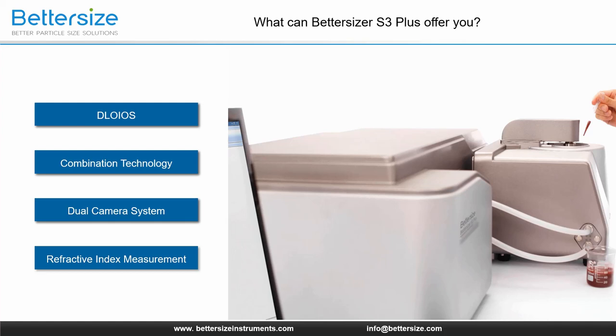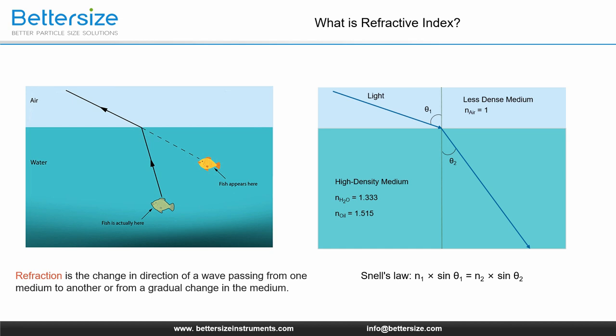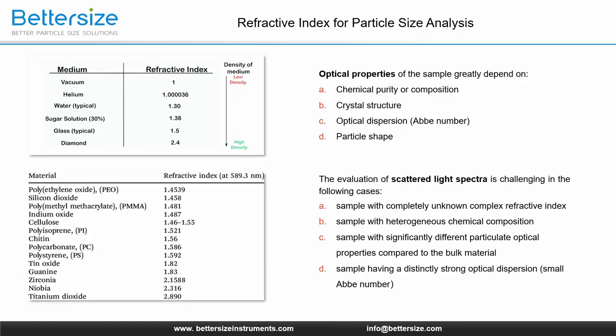I'm going to introduce a very special feature of the Bettersizer S3 Plus: refractive index measurement. The refractive index is a value calculated from the ratio of the speed of light in a vacuum to that in a second medium of greater density. As presented in the figure, an incident ray upon a plane surface separating two media is refracted when entering the second medium. So the refractive index is essentially a material constant. However, for the mathematical fit for particle size analysis according to Mie theory, the optical properties of the sample must be considered, which largely depend on chemical purity or composition such as impurities and mixtures, crystal structure and optical dispersion — meaning the influence of wavelength on the refractive index — and particle shape, which can cause reflection and scattering at irregularly shaped interfaces.